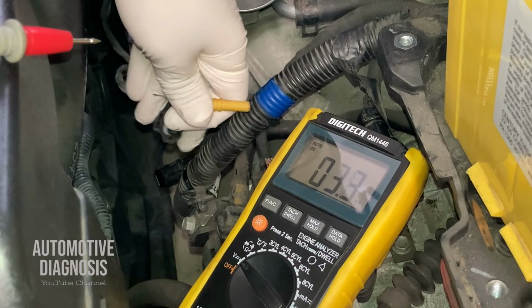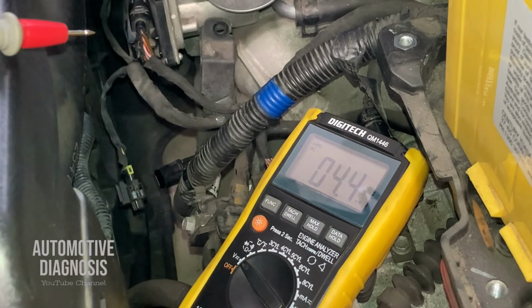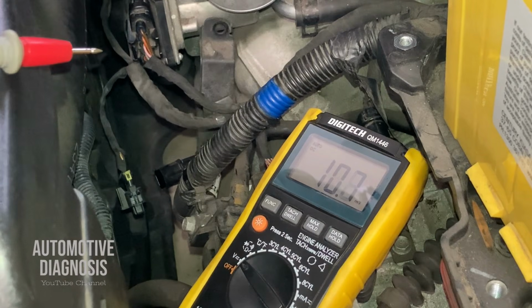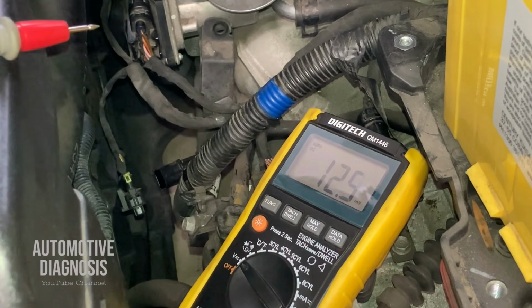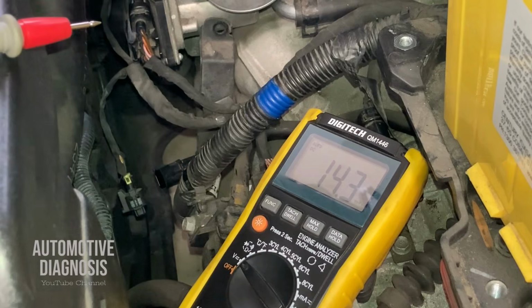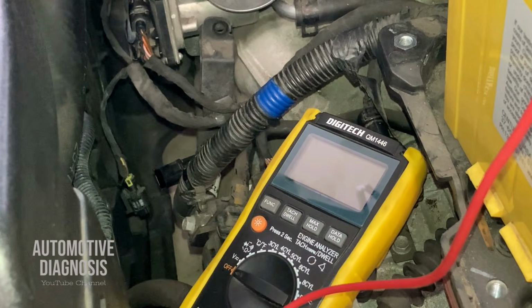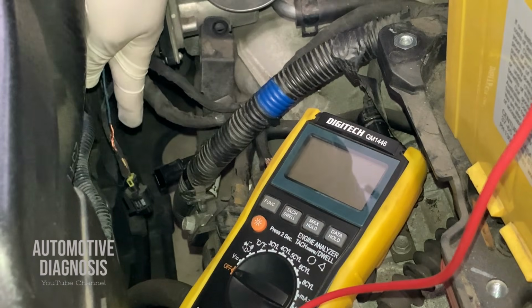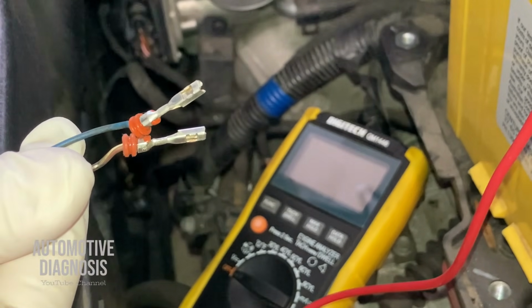So this is for checking the wiring, but can we check the sensor itself? Yes, we can test the sensor itself. We can check the internal resistance of the sensor to make sure if the sensor itself is okay or not. Because the sensor is located down there, for having a better measurement, I'm going to use these 2 pins. I will insert these 2 pins into the sensor connector so I will have a better, steady measurement.